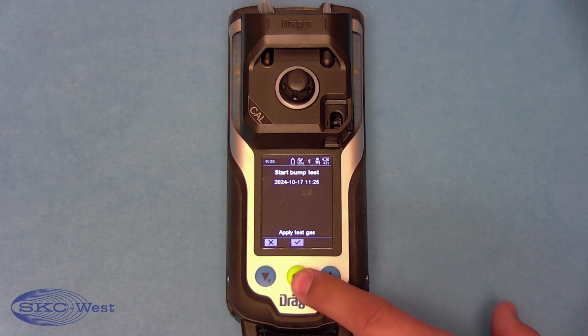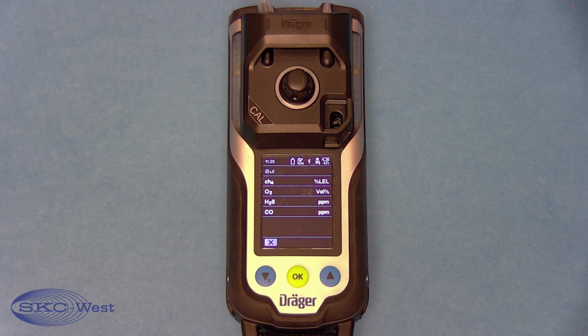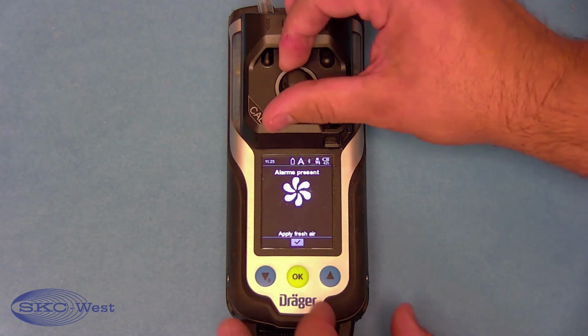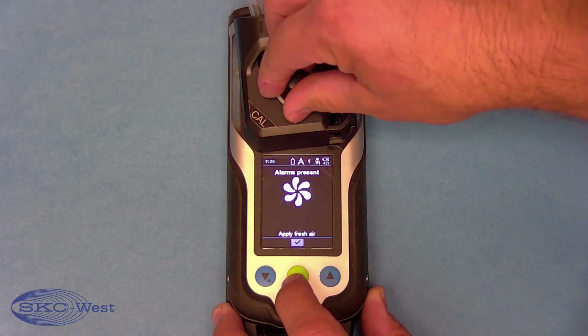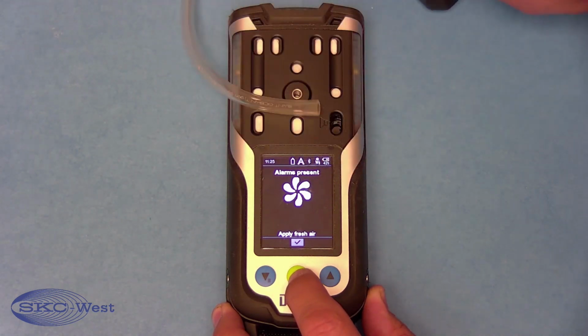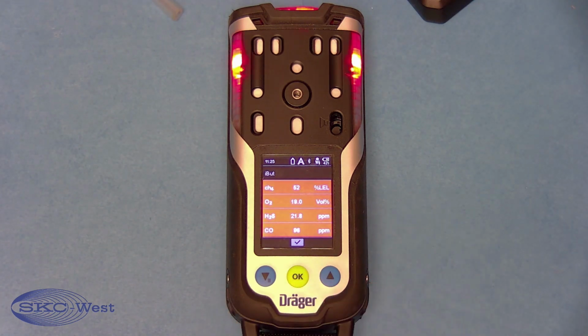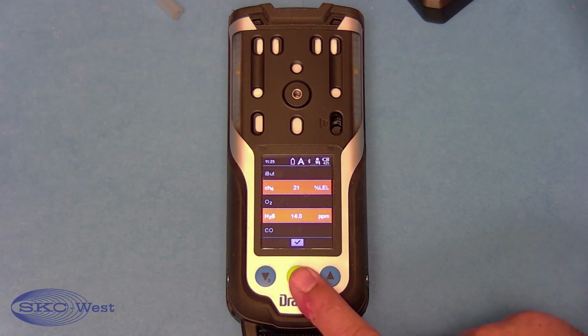What you're looking for here, once you hit OK and apply your gas, is all green check marks to the right of each sensor. Once you obtain those, you will shut off your gas and hit OK on the instrument while removing the calibration adapter. You can hit OK again one more time and wave your hand over the sensor head until the sensors go back to 0.